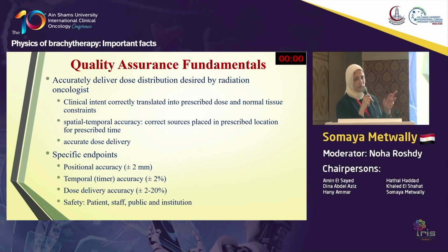When you start your day, you have to calibrate or do some quality assurance for your machine. The afterloader itself has multiple interlocks. You have to check the position of the source when it moves inside the transfer tube. You have to check the door is closed. You have to check the sound inside the room. You have to check a lot of interlocks regarding the treatment room.